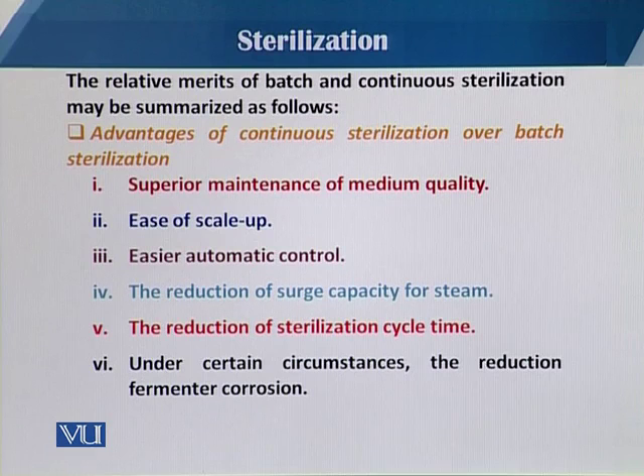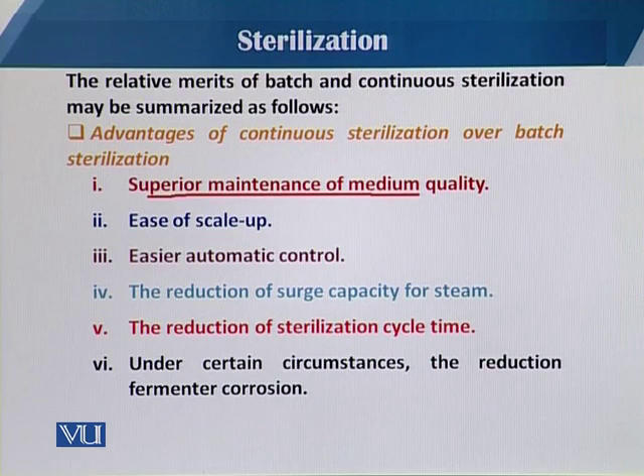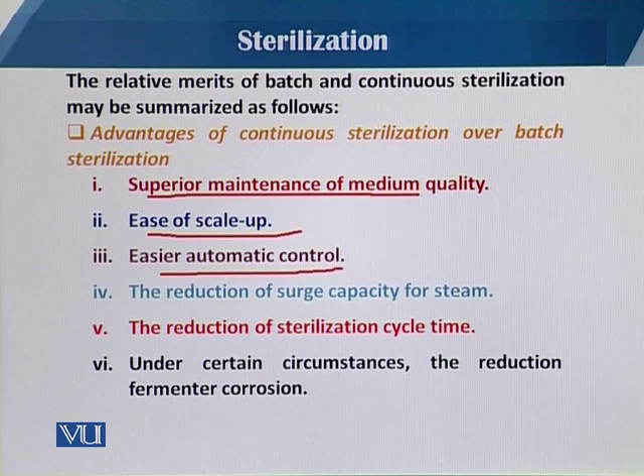The advantages of continuous sterilization over batch sterilization include: superior maintenance of medium quality, because we can apply high temperature for a short time. Additionally, it offers easier scale-up, easier automatic control, reduction of surge capacity for steam, and reduction of sterilization cycle time.